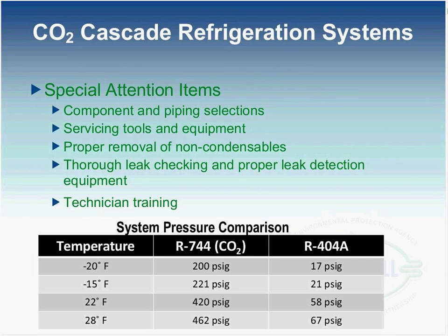Touch on a few key attention items that need to be considered when you're looking at a system like this. First off is component and piping selections. Make sure that all of the components and pipes are selected such that they're able to withstand the higher pressures that are found when you are operating with CO2. Secondly, make sure that the servicing tools and equipment are compatible. One thing I'll specifically note there is that we very strongly recommend that low loss fittings are not used on any gauges or testing equipment, because they can suffer major damage, as they're not designed to operate at the pressures that you would see CO2 at a higher temperature.